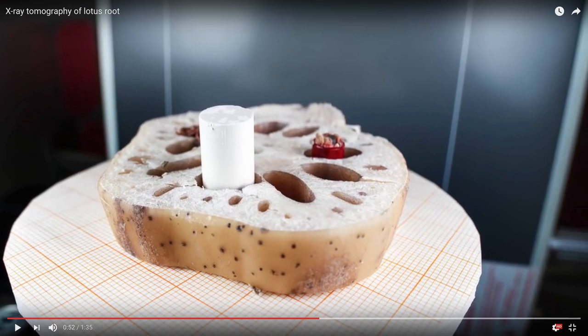Because we are doing 2D tomography for computational and simplicity reasons, it's important to check which row in the detector is on the same height as the x-ray source point where the x-rays come from. They emanate from one point as a cone. So if you use a row in the detector too high or too low, then the data is not coming from the same horizontal slice in the object. There is only one row in principle, ideally in the detector, that collects data from the same horizontal plane of the object when it's rotating. That's something Alexander will help you with, but it's just good to keep in mind that that's important.